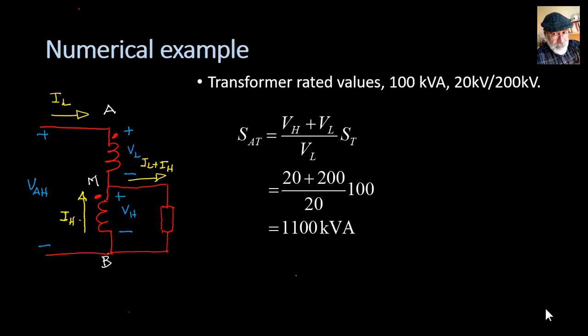Of course. How is it possible? That's possible because the transformer is feeding 100 kVA and the rest of the power, 1 mega volt amperes, is traveling galvanically from the high side to the low side of the auto transformer. That is why.